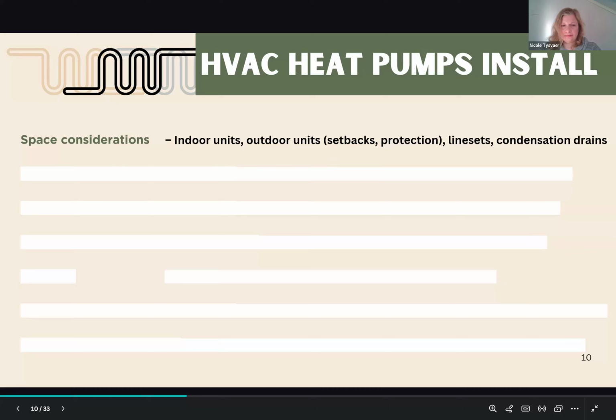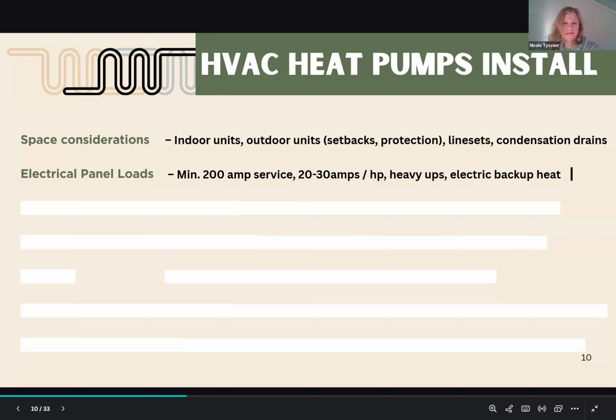Lastly, you want to check out your electrical panels first. As you size your equipment, generally you're going to need a 200 amp service. Some of these older houses, you're obviously going to need to heavy up. Your outdoor units on heat pumps can run 20 to 30 amps. Electric backup heat can run 40 to 50 amps. So you want to make sure your electrical panel can handle all the needs of your equipment. That might require getting a licensed electrician to upgrade the panel.